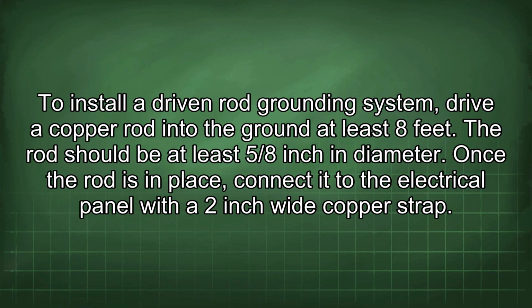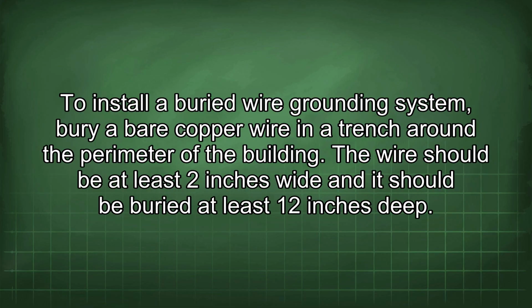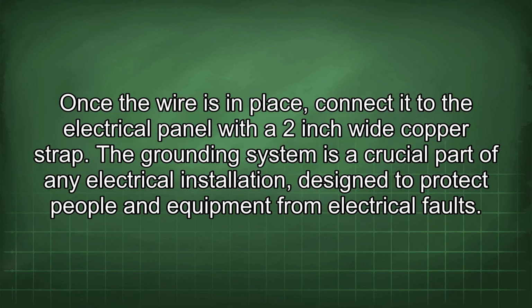To install a driven rod grounding system, drive a copper rod into the ground at least 8 feet. The rod should be at least 5/8 inch in diameter. Once the rod is in place, connect it to the electrical panel with a 2-inch wide copper strap. To install a buried wire grounding system, bury a bare copper wire in a trench around the perimeter of the building. The wire should be at least 2 inches wide and it should be buried at least 12 inches deep. Once the wire is in place, connect it to the electrical panel with a 2-inch wide copper strap.